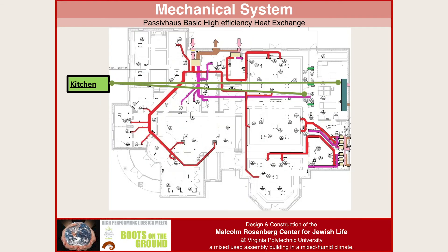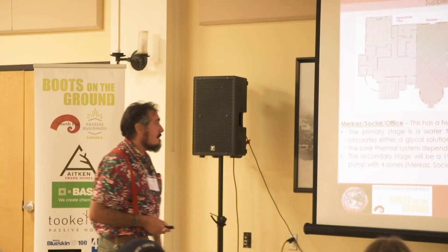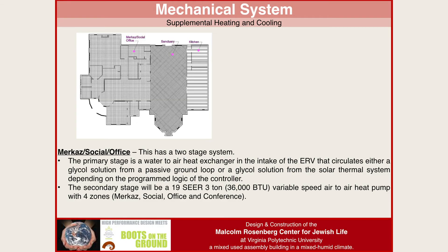Here's the hood with passive vents that bring in outside air under both sides and exhaust back out. That was our ventilation strategy. In Passive House we use mechanical ventilation with heat recovery. An energy recovery ventilator is like a heat recovery ventilator but also transfers latent humidity and moisture between airstreams — and in Virginia, we have a lot of moisture.